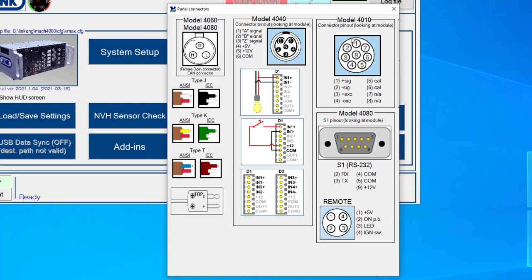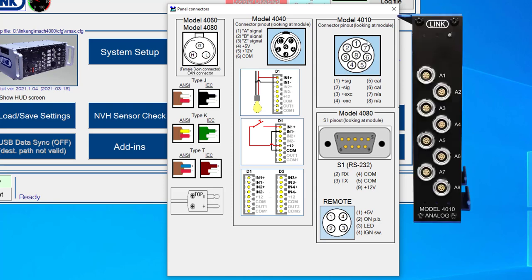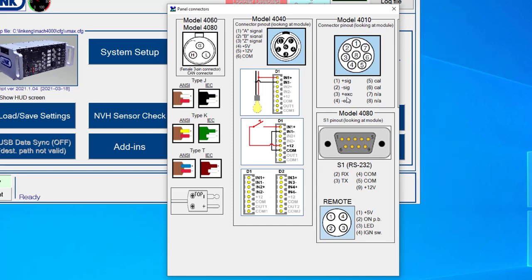So the 4010 analog input module you can see is an 8 pin Lemo connector, and it gives you the pinout of plus minus excitation, plus minus signal. Pins 5 and 6 are reserved for calibration, so those pins can be shunted or shorted together for shunt resistance type calculations.